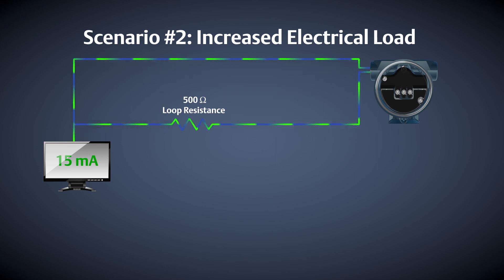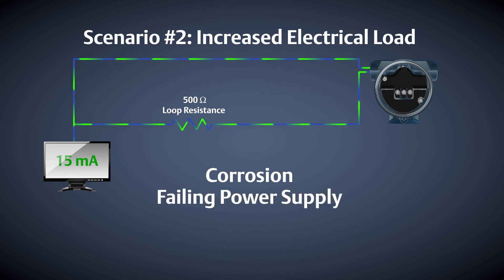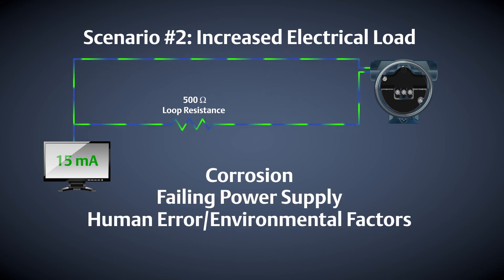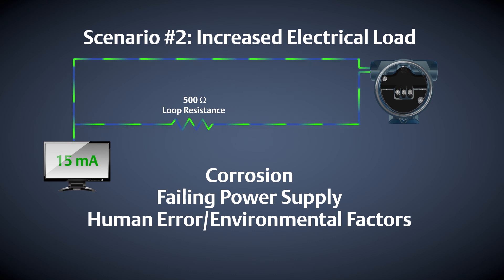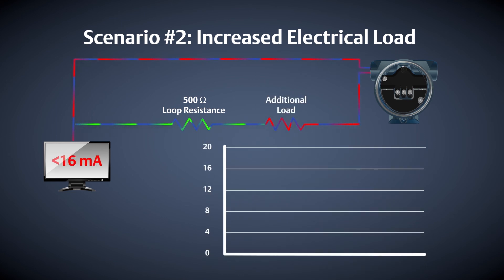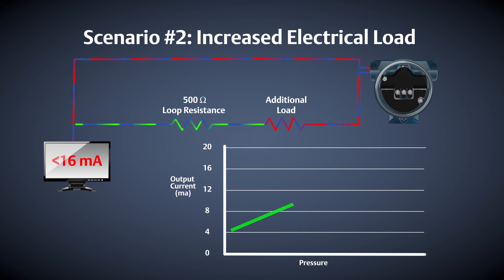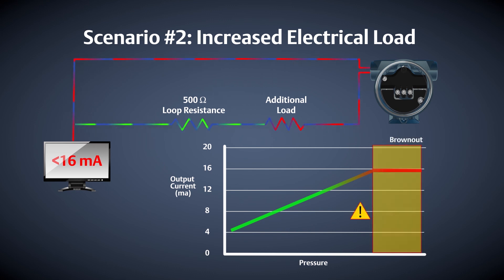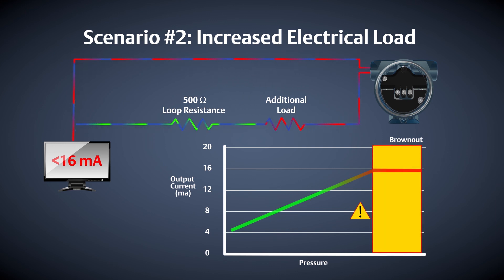The second scenario is an increase in the electrical load of the wiring loop. This can be caused by corrosion, a failing power supply, human error, or other environmental factors. In this scenario, the electrical loop was designed to have 500 ohms of resistance. When additional resistance is inadvertently added to the control loop, the reliability of the control loop is compromised. With an increased wiring loop resistance, there may not be enough voltage for the transmitter to drive the loop to the proper milliamp value or even to an alarm state. In this example, the transmitter is unable to go above 16 milliamps.